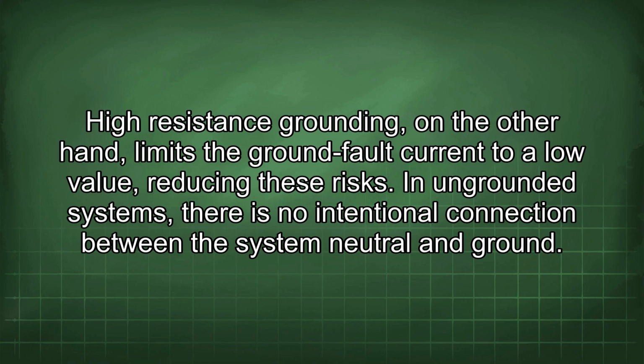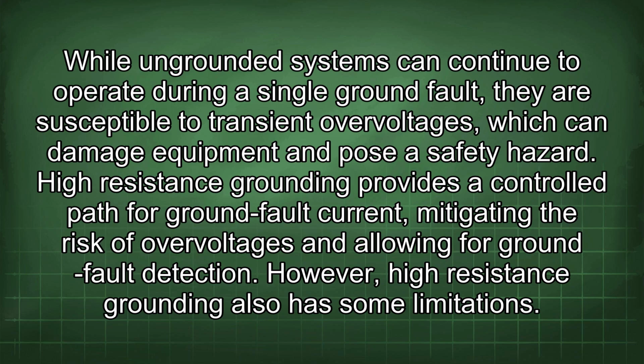In ungrounded systems, there is no intentional connection between the system neutral and ground. While ungrounded systems can continue to operate during a single ground fault, they are susceptible to transient overvoltages, which can damage equipment and pose a safety hazard. High-resistance grounding provides a controlled path for ground fault current, mitigating the risk of overvoltages and allowing for ground fault detection. However, high-resistance grounding also has some limitations.